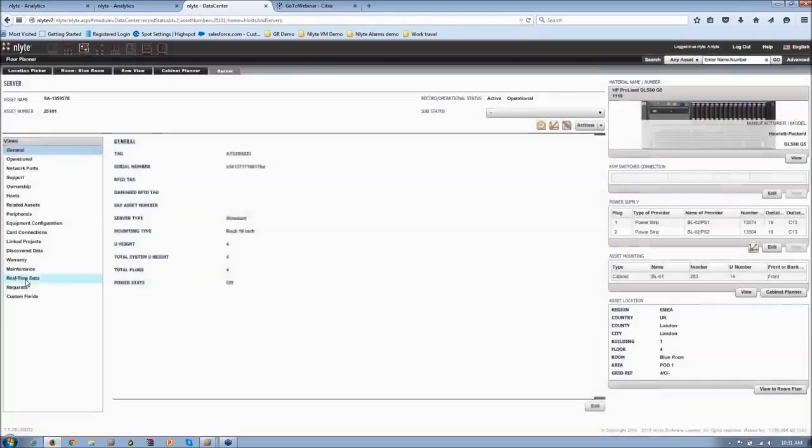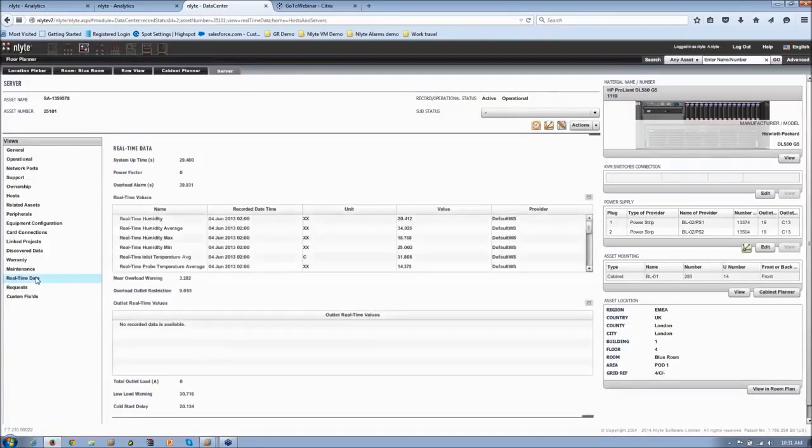When we're talking into DCM, we're actually bringing back the information. We're putting it on the real-time metrics inside Nlyte against the device. So we're reading in the inlets or the real-time values that are coming into the Nlyte system. They're being stored against the devices, tracked against the devices, and all the attributes that we're bringing back in, so the CPU and the memory as well will also be tracked inside there.